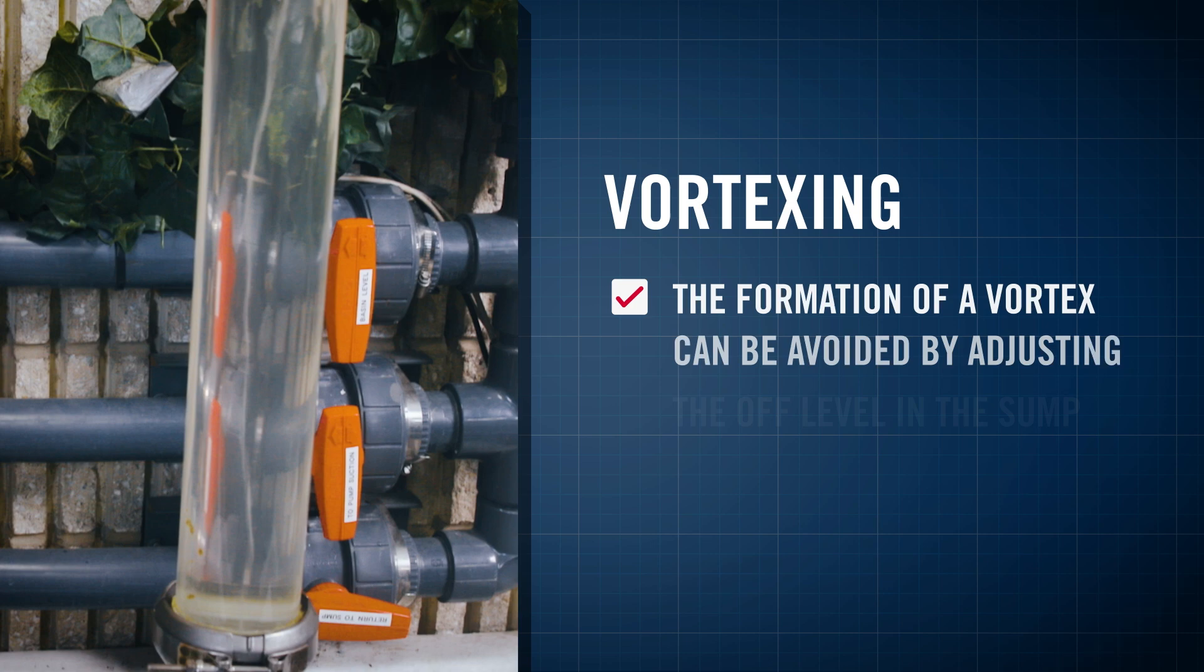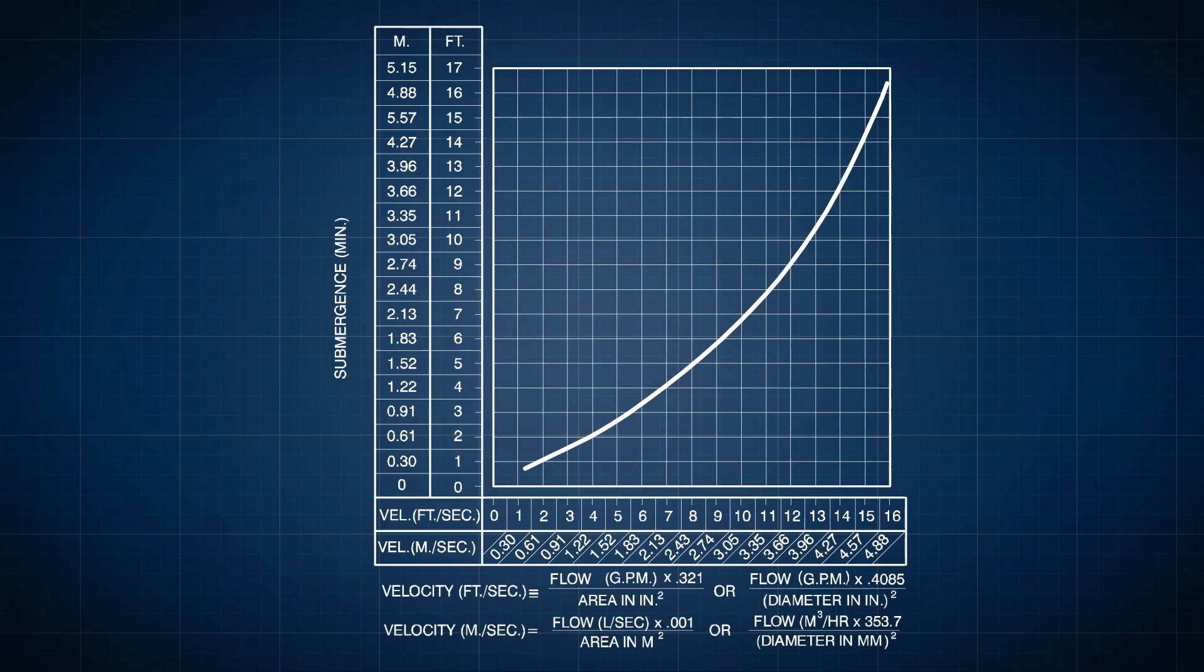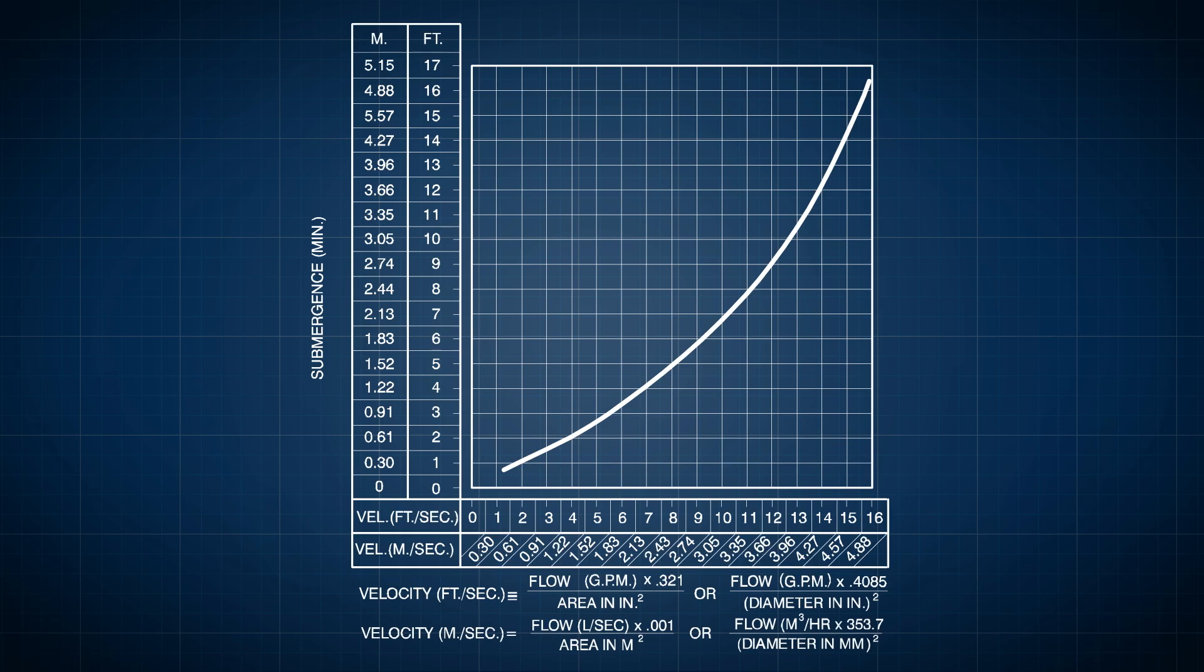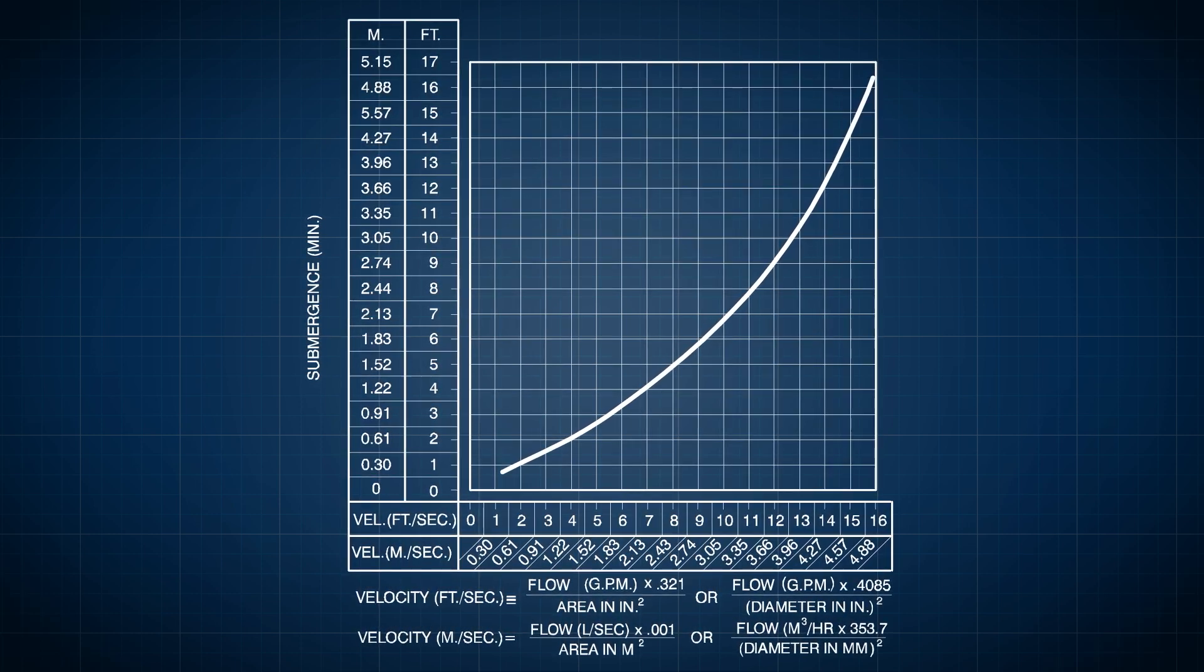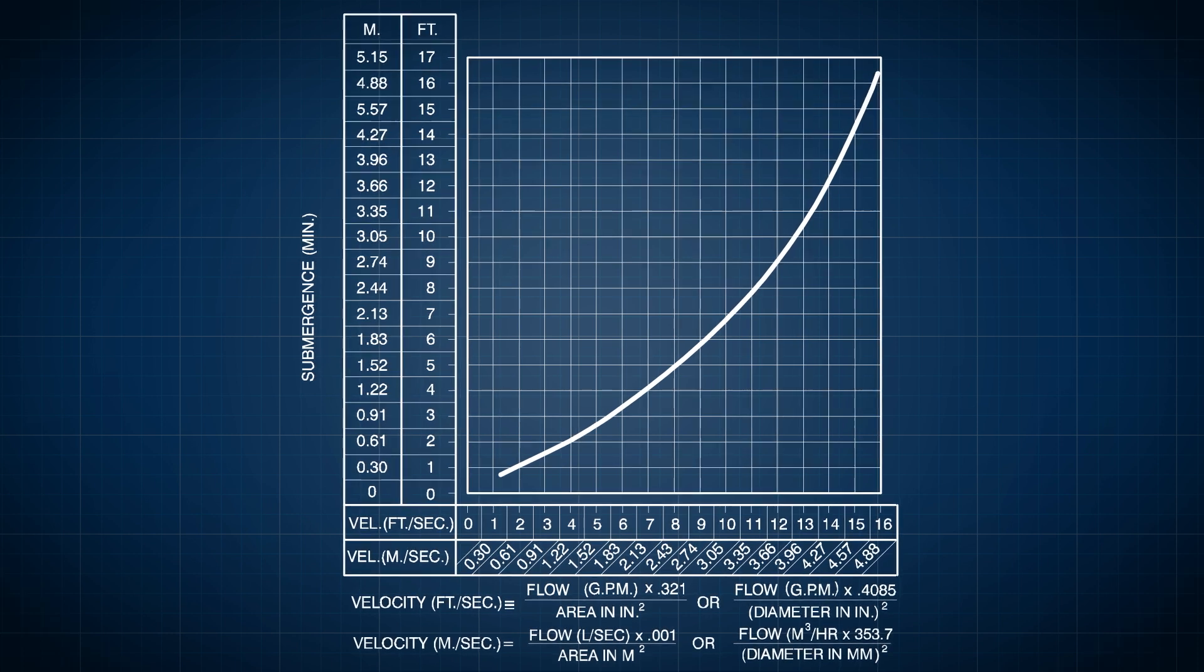The formation of a vortex can be avoided by adjusting the off-level in the sump. All Gorman-Rupp self-priming pump manuals include an easy-to-read chart that recommends the minimum submergence required to prevent a vortex from forming.